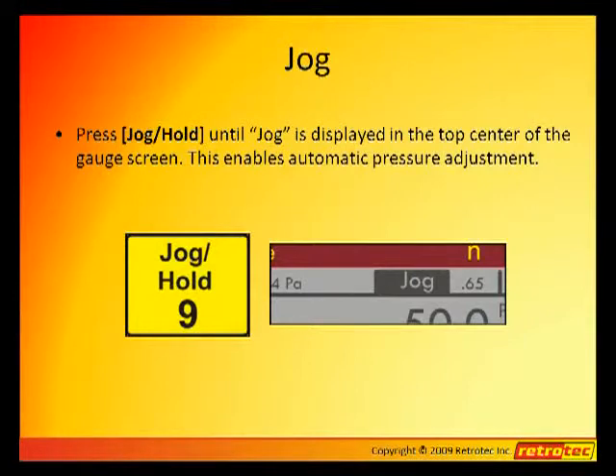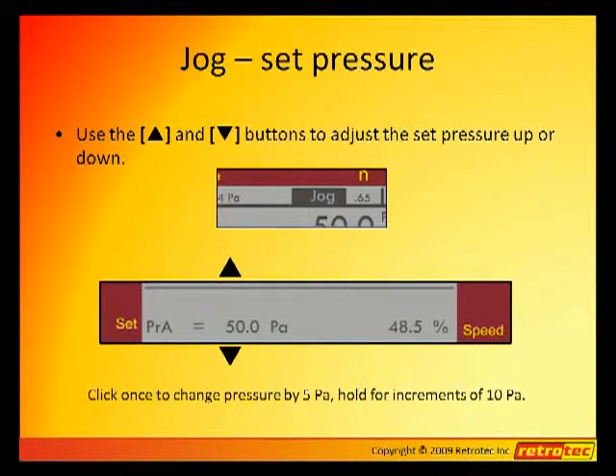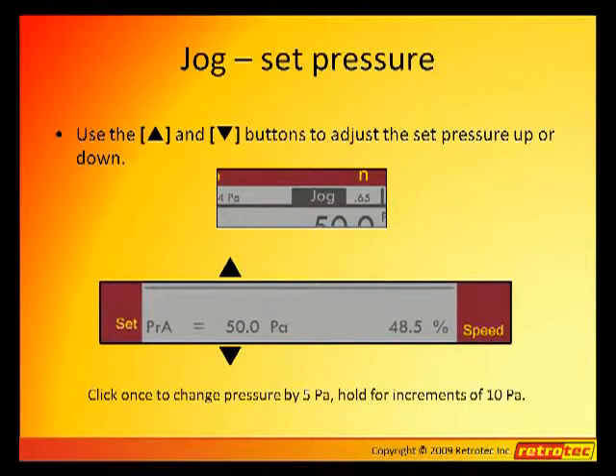An advantage of this Set Pressure technique is that a series of test pressure points can be measured, starting at a pressure of, let's say, 60 Pa, and each successive pressure below that can be established merely by clicking the down arrow — very much like the way you would operate your TV to change channels. We click once to create a Set Pressure adjustment of 5 Pa, and if we hold it down, we get a Set Pressure adjustment of 10 Pa.